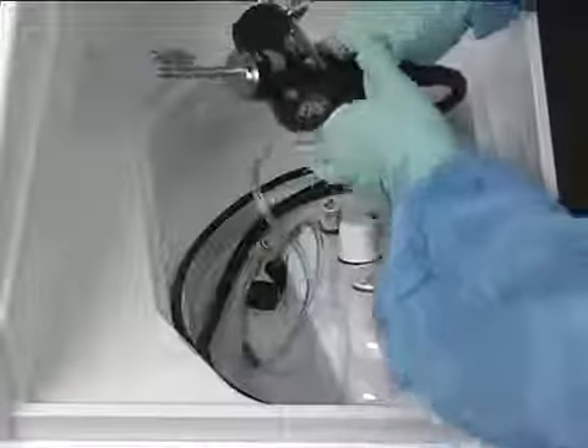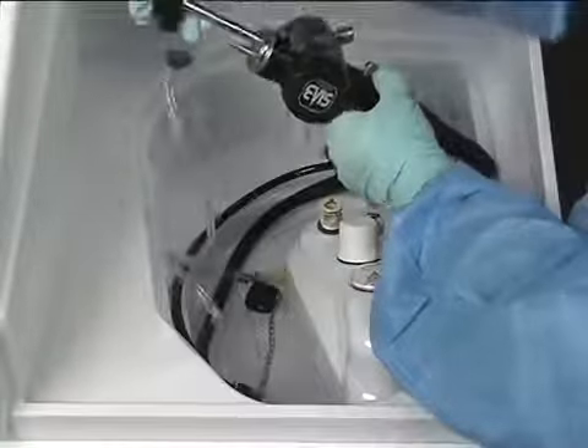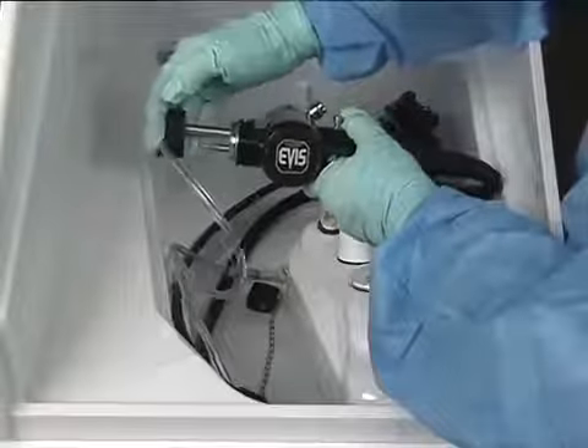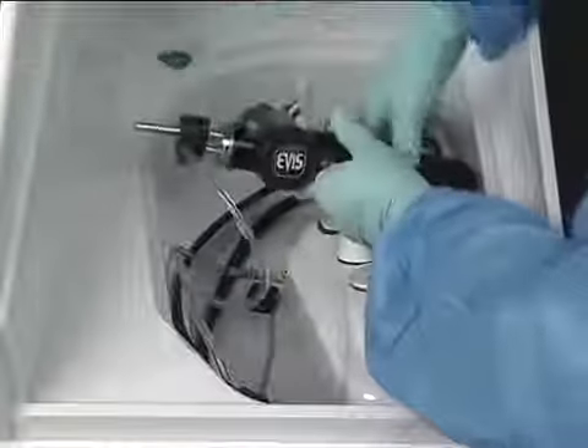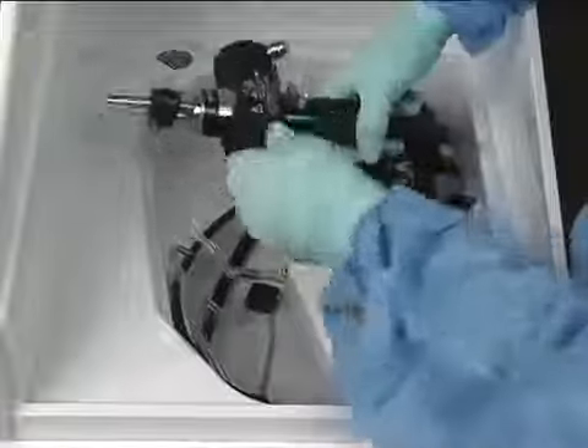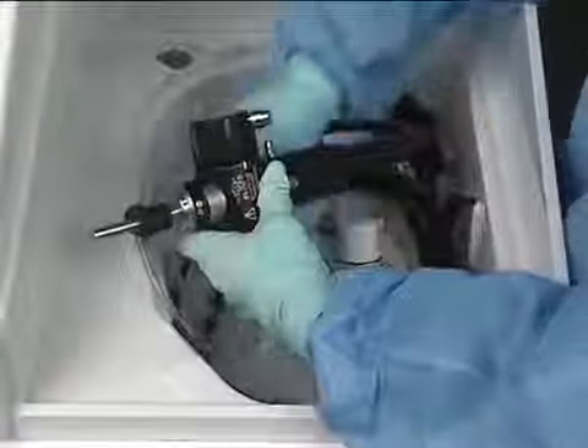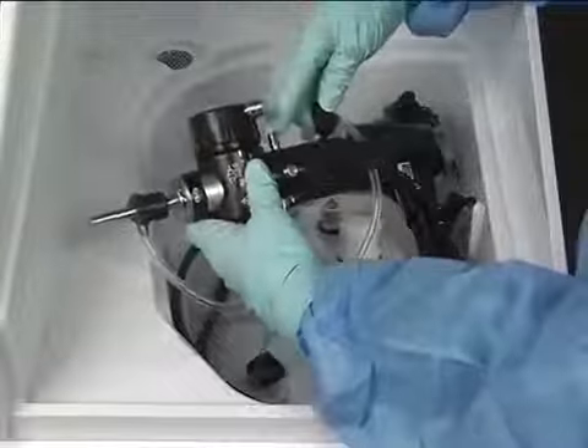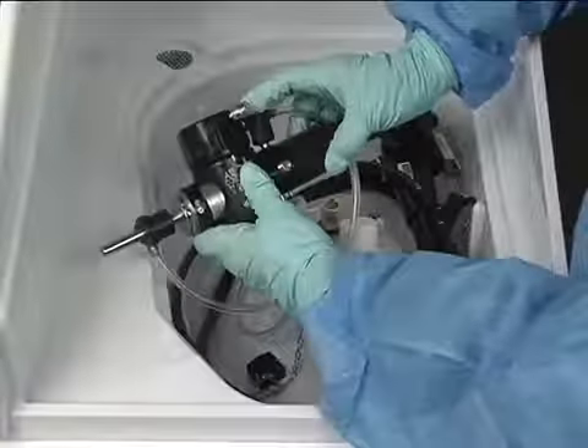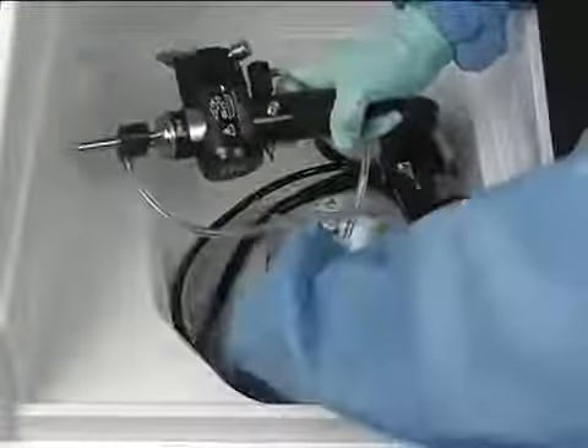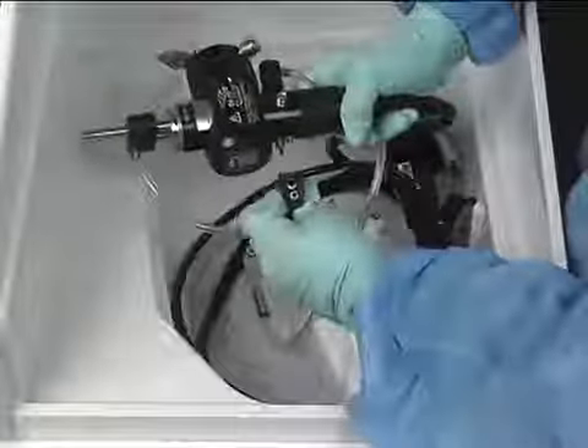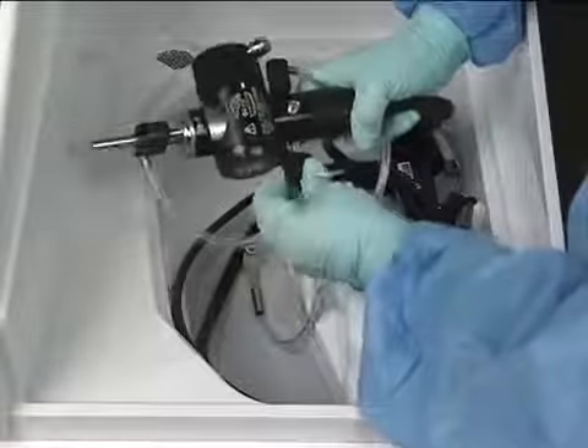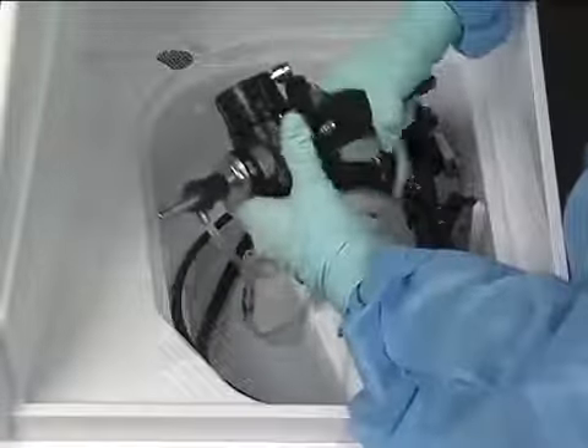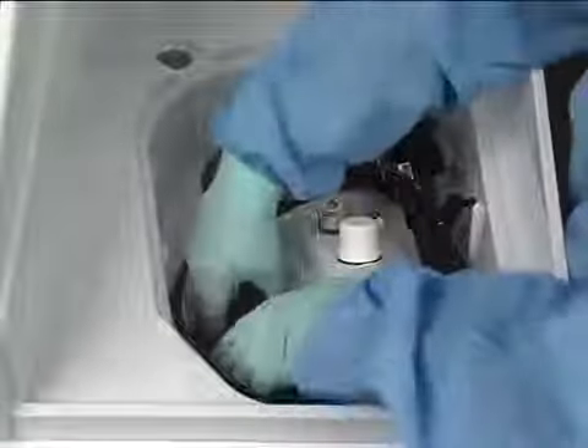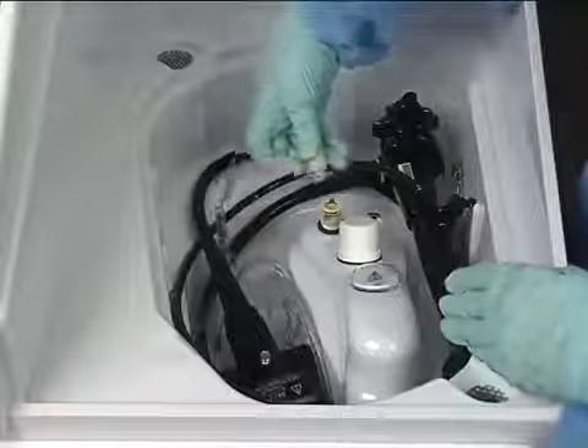Connect the air port on the hookup to the air pipe on the endoscope. Connect the suction channel tube on the hookup to the suction connector on the endoscope. And connect the plug to the air and water supply connector port on the endoscope. Attach the inflow end of the basin hookup connector to the basin connector.